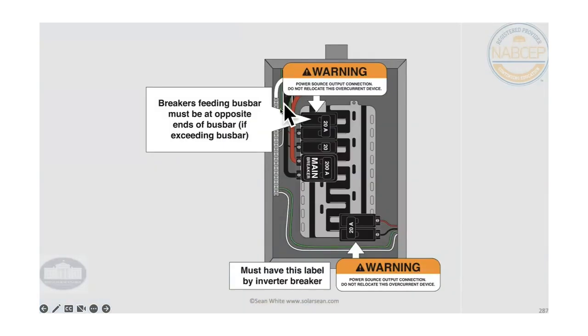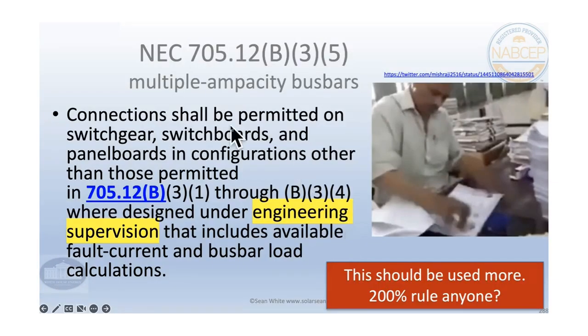Center-fed bus bars, which you don't see as much on the East Coast, but they're kind of common in California. People spent millions of dollars replacing these things until they came up with an amendment in 2016 to the 2014 NEC. And now for residential, we can do the 120% rule on center-fed bus bars. The difference in the 2020 NEC is that you can put breakers on both sides, and before they required them all to be at the same end, which was actually worse, from an engineering point of view. So it's even better for them to be on opposite sides. It doesn't mean you get the 140% rule by some trick or anything like that, but that's what we're dealing with there.